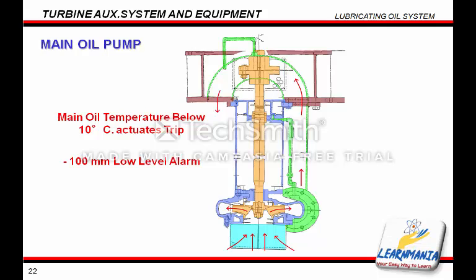This figure illustrates the MOP. Oil passing the suction strainer of the pump is sent to the discharge piping using the centrifugal force of the impeller. A vent pipe is located in the upper part of the discharge piping. Discharge oil is used to lubricate the upper bearing of the pump shaft. Note that if the oil temperature is below 50 degrees Fahrenheit, the pump will not operate, nor will it operate in the event of a low oil level alarm.